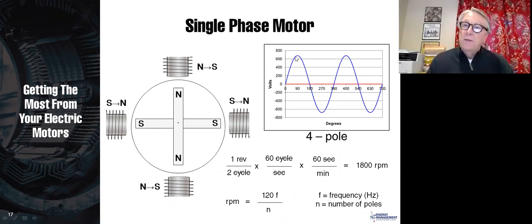Now, in this case, when the electric waveform, the voltage, is positive, then this magnet on top becomes a north pole. The magnet on the right becomes a south pole, the magnet on the bottom a north pole, the magnet on the left a south pole. But the rotor in the middle, because it also has 4 poles, is not going to rotate 180 degrees. It's only going to rotate 90 degrees. Now, when we change the electric utility power from positive to negative, then the top one changes from a north pole to a south pole, the right one from a south pole to a north pole, and so on, and we'll rotate another 90 degrees. Which direction? Don't know, but once we push it and get it rotating, then it will continue rotating in that direction. And how fast will it go?